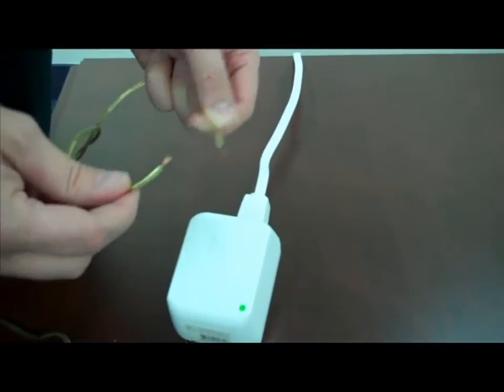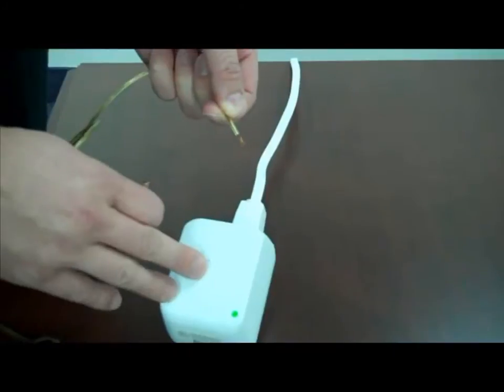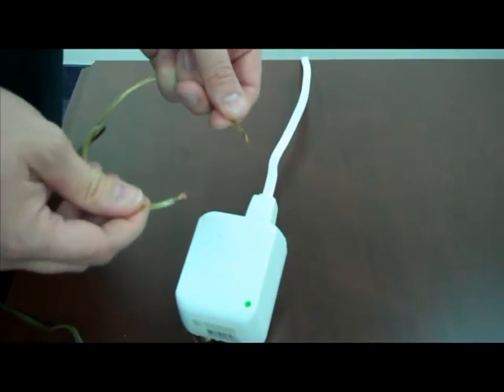The green light immediately comes back on, so we have power again. We didn't blow the fuse out. The PTC opened up, and once it cooled off, it made contact and the transformer is able to continue to output power.